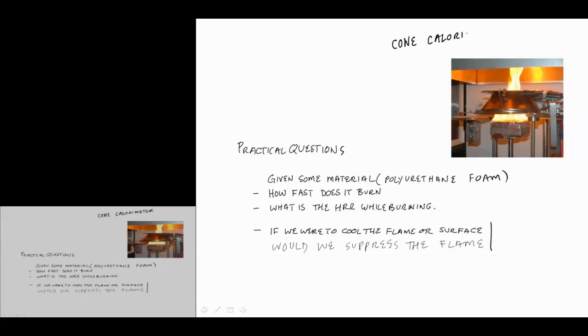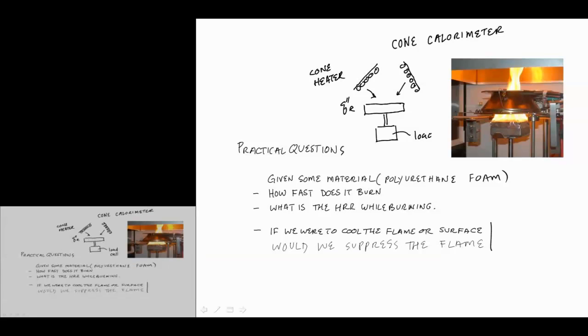And it's called a cone calorimeter because there's a radiant cone-shaped heater system, so it's a cone heater under which there's a well-specified heat flux on some sample that's located under the heater. The sample is typically on a load cell.